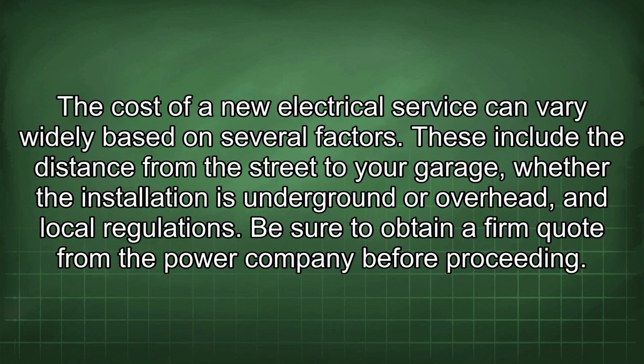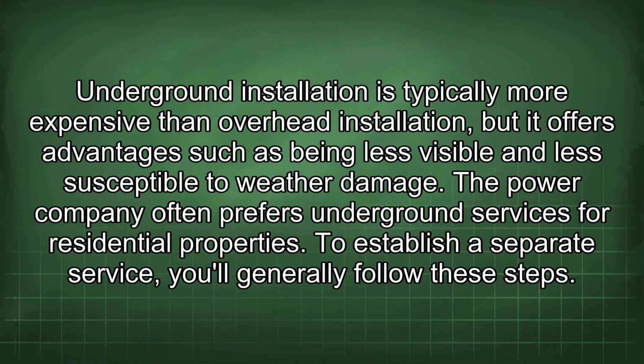The cost of a new electrical service can vary widely based on several factors. These include the distance from the street to your garage, whether the installation is underground or overhead, and local regulations. Be sure to obtain a firm quote from the power company before proceeding. Underground installation is typically more expensive than overhead installation, but it offers advantages such as being less visible and less susceptible to weather damage. The power company often prefers underground services for residential properties.